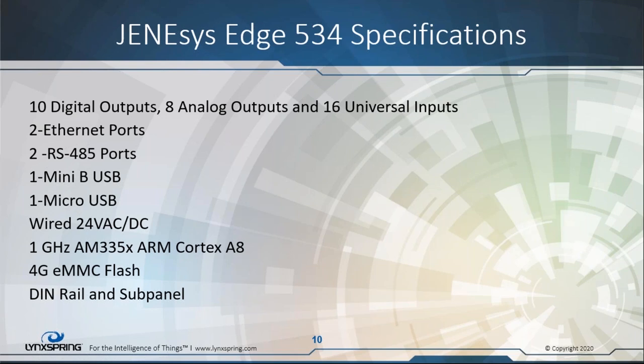There are 2 Ethernet ports, primary and secondary, of 10 base 100. Two RS-485 ports are also available, one mini and one micro USB. We support power from 24 volt AC and 24 volt DC supplies, class 2 supply transformers. Also, I want to make you aware that this is a full wave rectified device, so we want standalone or dedicated power supplies for the controller.